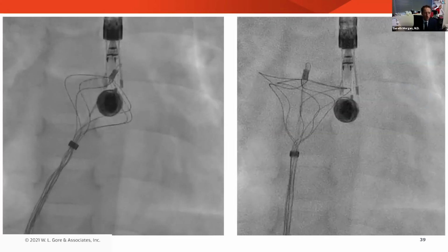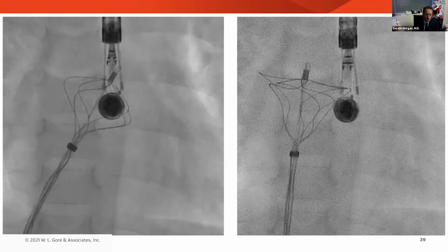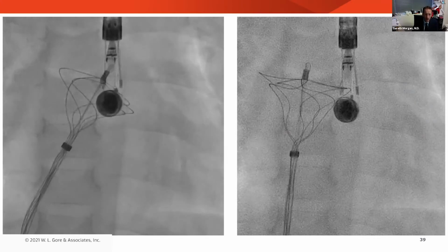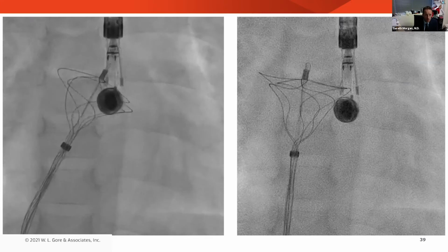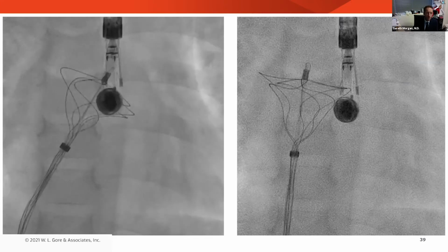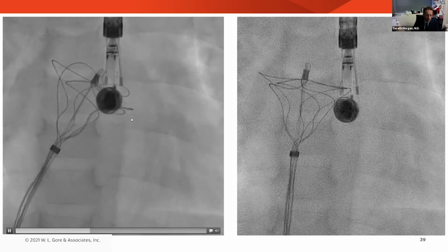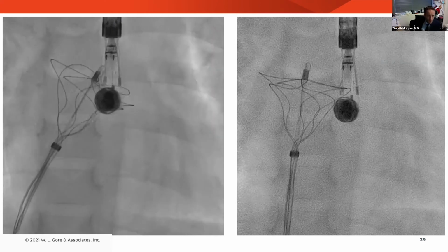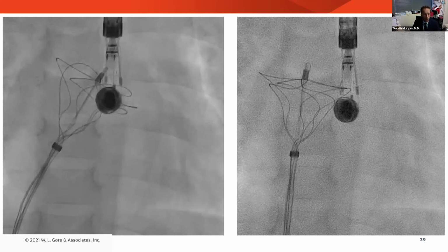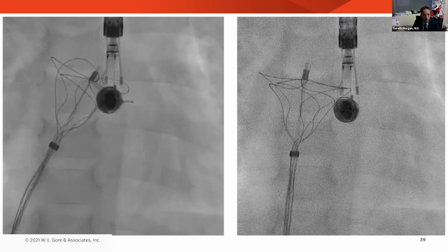So this is important. The position that the handle is in when you're deploying the device can really help you or hinder you. So in the panel on the left here, the device is being extruded with the handle in a neutral position, so as it lays on the table with the controls of the handle facing up towards the operator.